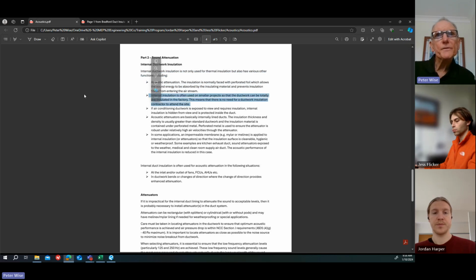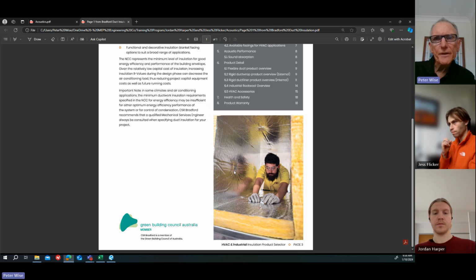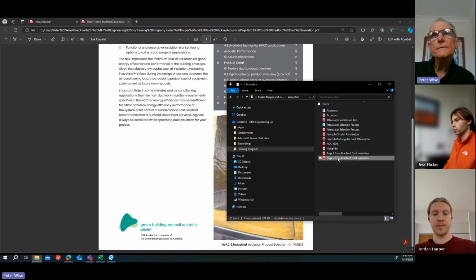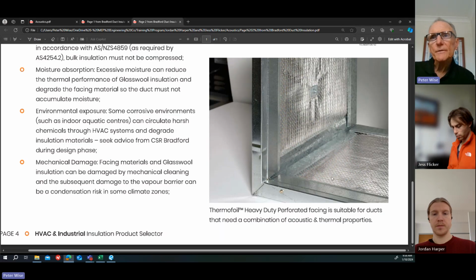Internal insulation is often used on small projects, so the ductwork can be totally pre-insulated in the factory. This means there's no need for a ductwork insulation contractor to attend the site. I'll just show you a couple of pictures, if you haven't seen it. Have you guys been to a duct factory? I think you have, haven't you? Yeah. So you probably saw them doing this, doing the internal insulation? Okay. So that's in the process there. There's another picture here of what it looks like basically when it's finished. So they put angles or trims, flashings on the long sides and at the joints just to cover up the raw edges.